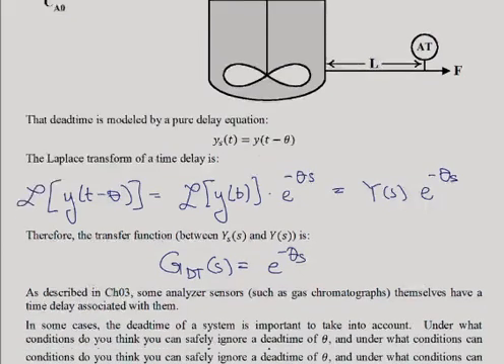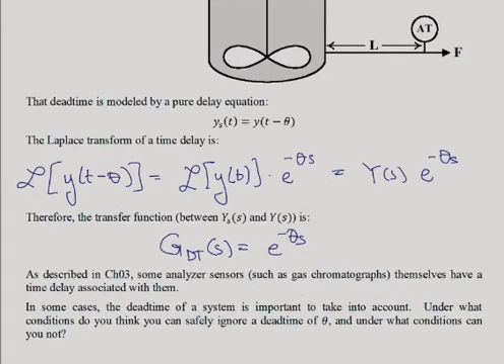Now, as we described in earlier topics, some analyzer sensors, things like gas chromatographs, themselves have a time delay associated with them, and so just theta would change in this relationship. So you have time delay, or dead time, because of the flow through there, and dead time because of the analyzer sensor itself.